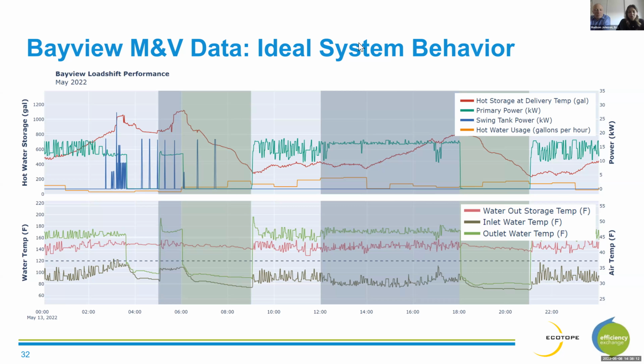And then lastly, some important points at Bayview are the inlet and outlet water temperatures of the heat pump. Systems like the Mitsubishi QAHV require large temperature differences between the inlet and outlet water temperatures. So if we see inlet water temperatures that are too high, it does impact the system's capacity and its COP. And so you can see we have a range of around 80 to 120 degrees, and that's a little bit higher than we would like to see. So this did have an impact on system performance, but it's something that we've been working with Mitsubishi on. And that's one of the exciting things about this project, is because we're looking at the system in such detail, we can find things like this and work with manufacturers to improve for future installations.